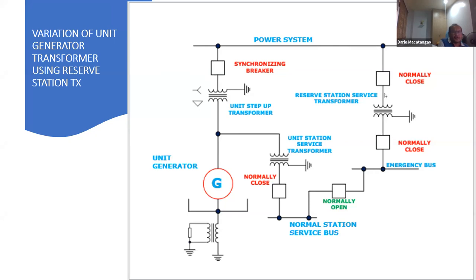So during normal operating situation, this breaker is closed, this breaker is closed, this breaker is closed. This is your emergency bus. This is normally open here. And then this is your normal station service bus. All the emergency loads are powered from these emergency buses, okay? Especially in the nuclear, they have lots of emergency stuff. So this is powered on this emergency bus. Now, this station service bus here feeds the power needed to support the operation of the generator. It's a normal station service bus.